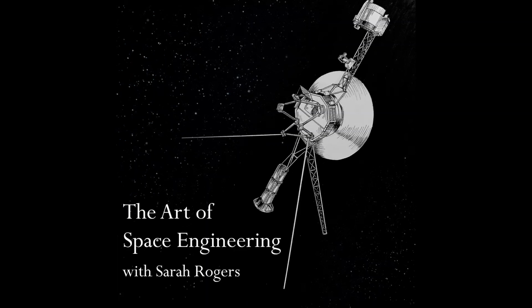And then when you've got hardware that you are in the process of building that you know is relatively clean at this point, you have a number of tools available to you to keep it clean and to make it cleaner. To keep it clean, we have cabinets that we use that have a continuous flow of very clean, dry nitrogen gas. That's called a purge environment. So you put stuff into these cabinets that have a positive pressure, so that stuff can't get into them. It only blows the nitrogen out and keeps the equipment that's put in there very clean indeed.